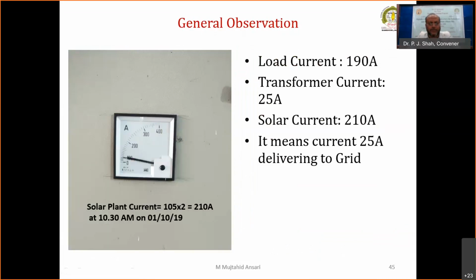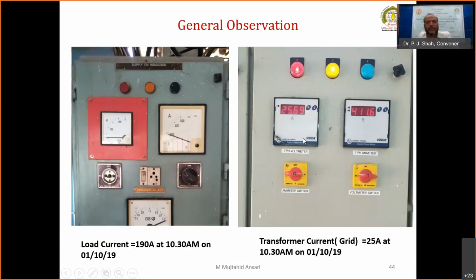Okay, now this is again the same thing. The solar plant current is around 210 ampere, so the current delivered by the solar plant is 200. Load is say 190. It means the 25 ampere current, I am not taking from the grid, rather I am delivering this current to the grid, since the solar current is more than the load. So the rest of the current, nearly 25, is going to be delivered to the grid system.